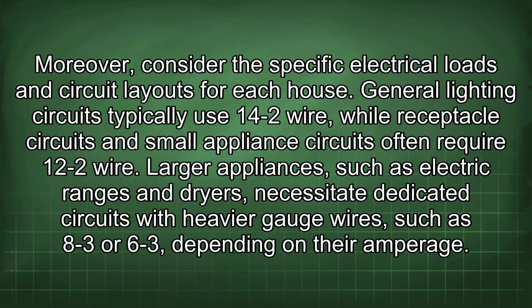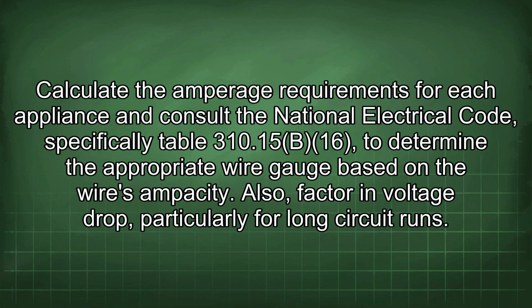Moreover, consider the specific electrical loads and circuit layouts for each house. General lighting circuits typically use 14-2 wire, while receptacle circuits and small appliance circuits often require 12-2 wire. Larger appliances, such as electric ranges and dryers, necessitate dedicated circuits with heavier gauge wires, such as 8-3 or 6-3, depending on their amperage. Calculate the amperage requirements for each appliance and consult the National Electrical Code, specifically Table 310.15(B)(16), to determine the appropriate wire gauge based on the wire's ampacity.